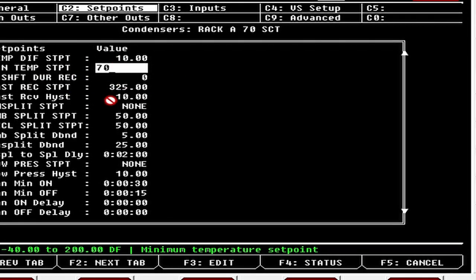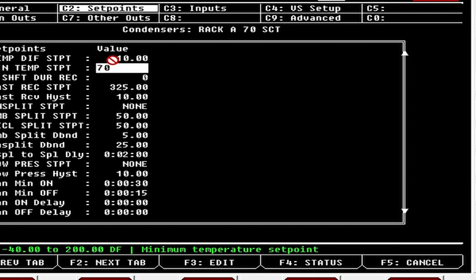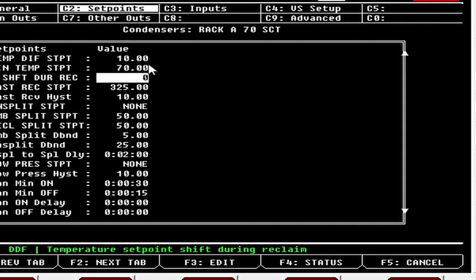On the flip side, Emerson doesn't have a maximum set point — Danfoss, Micro Thermo, and others do, but not Emerson. So if something happened to the outside air temp sensor and it was reading 120 degrees, it would give you a 130-degree condenser set point, which is insane — you're just wasting energy. I always fake out this number, and we'll go over how to do that during the flexible combiner video.